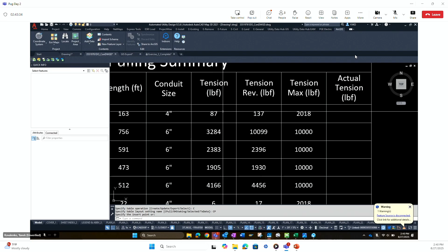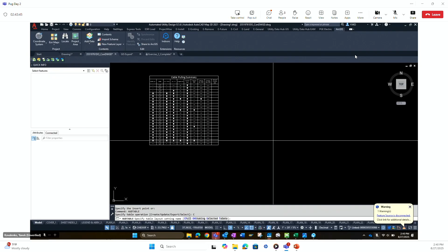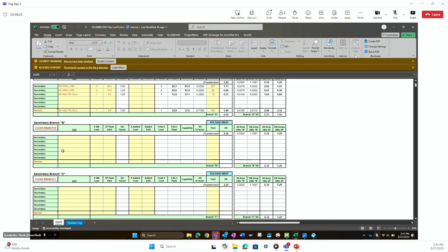In the same way, we would do our transformer tables. So volt drop flicker, we would have to create, run through Excel spreadsheets, fill out, this is what they would look like, fill out the transformer sizes, single phase or whatever the voltage is, fill out how many customers we've got, fill out the lengths of our secondary lines as well as services to our secondary enclosures, and then that would spit out information of volt drop, whether it's meeting volt drop, exceeding volt drop, and so on and so forth. And you can imagine this would have to happen at each transformer, and you would have to fill out all of these different branches depending on which way the secondary or service is branching out of the transformer.